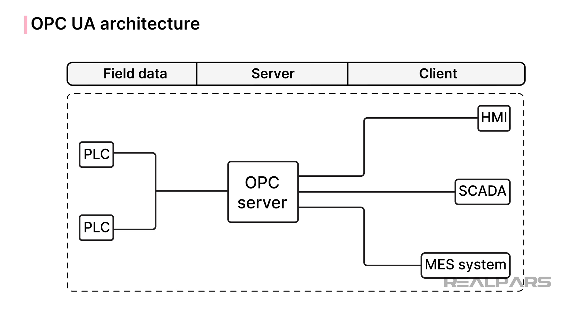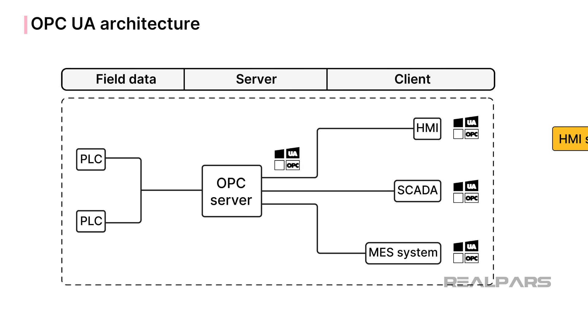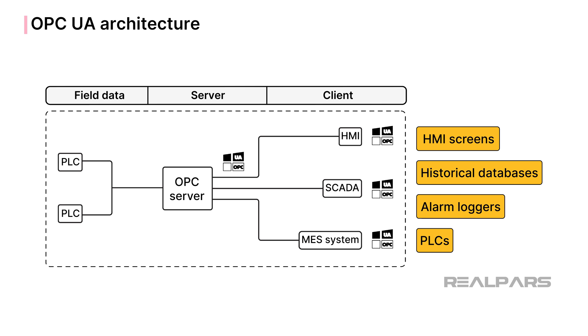To use OPC UA in your control system, you need OPC UA server software to connect to the data sources, such as PLCs, application computers, and HMI stations. You also need OPC UA client software to interact with the OPC UA server and set up subscriptions for periodic data access. This data will be used to store the collected data for use on HMI screens, historical databases, alarm loggers, PLCs, or other applications.